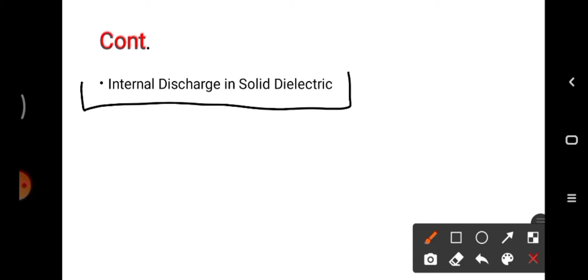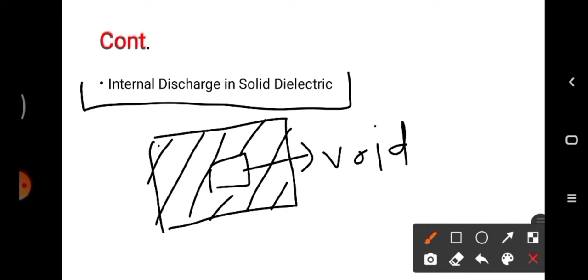Next phenomenon is internal discharge in solid dielectric material. The main reason for internal discharge is the presence of voids and cavities inside the solid dielectric material. Consider a solid dielectric material. Inside the solid dielectric material, a cavity or void is present. This is the void and this is the solid dielectric material. Permittivity of the solid dielectric material is given by epsilon 1 and permittivity of the void is given by epsilon 2. In this case, the permittivity of the solid dielectric material is greater than that of the void, that is, epsilon 1 is greater than epsilon 2. Whenever high voltage is applied, the electrical stress moves towards the void. As a result, the property of the solid dielectric material becomes spoiled, the material becomes conductive and breakdown occurs inside the solid dielectric material.